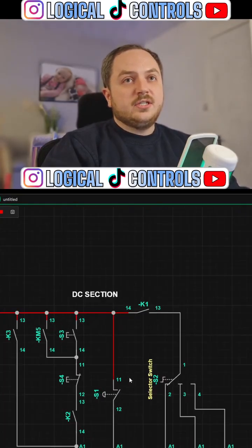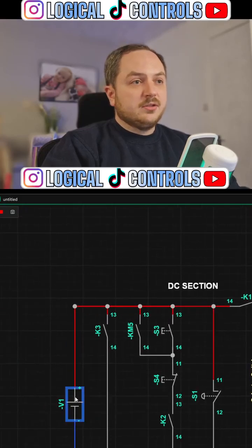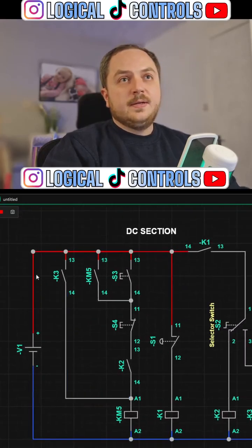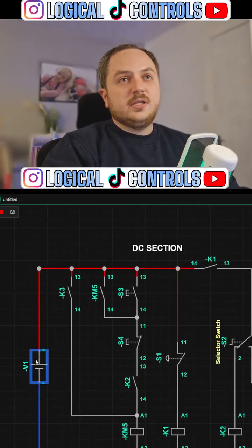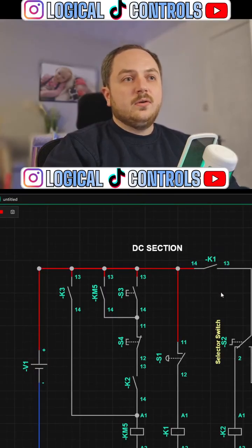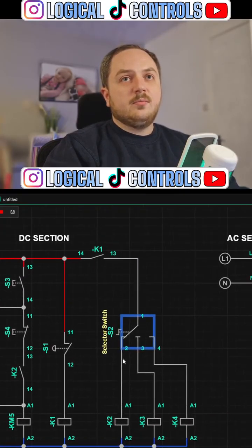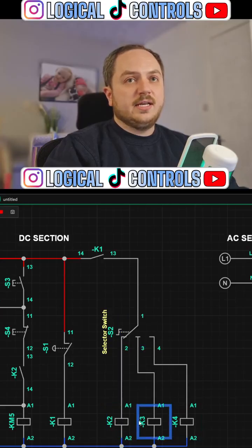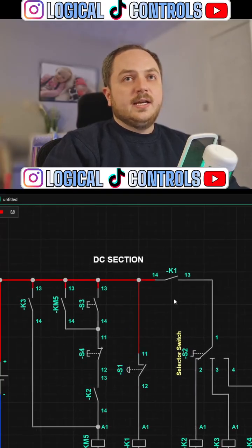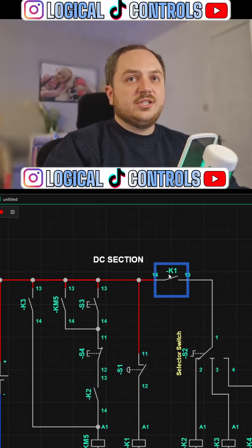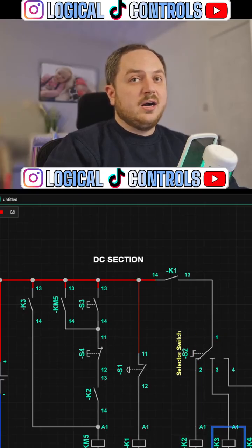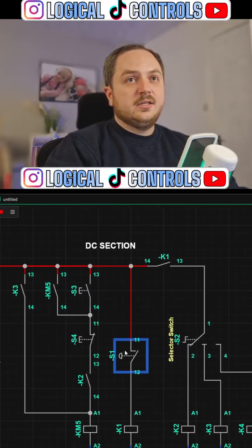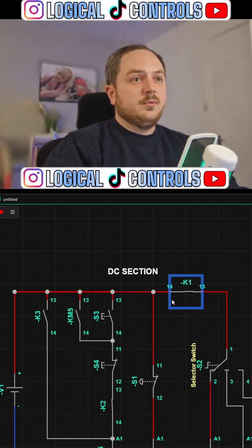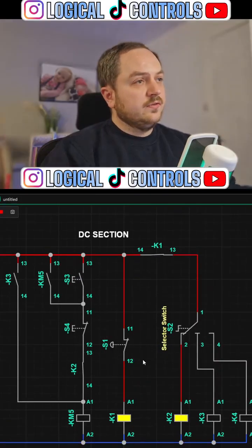But the way that works in this circuit is the power supply is here, the battery. I think you can all see that, all right? Yeah. The battery comes along into K1, and then it goes through K1 before it gets to the selector switch and to the relays that do the controls. And by the fact that that's in that position there, in series with every single part of them, those relays, if that K1 ever opens, it cuts everything off.